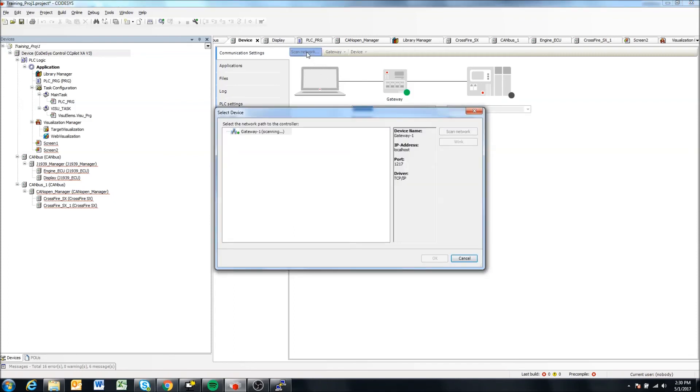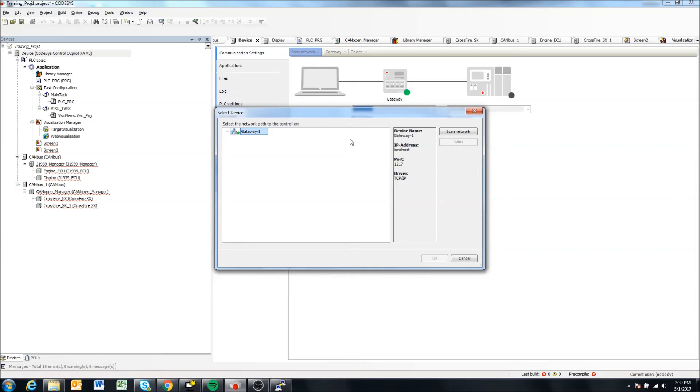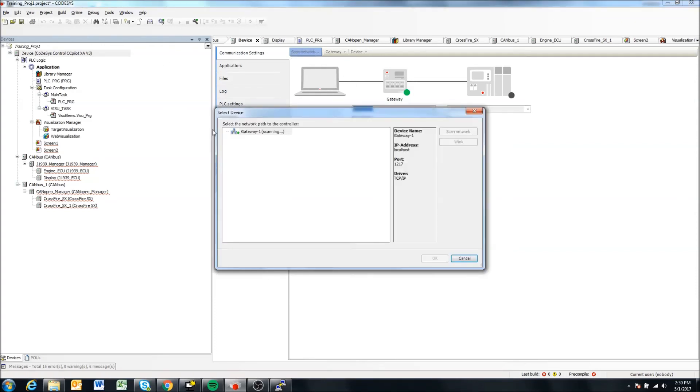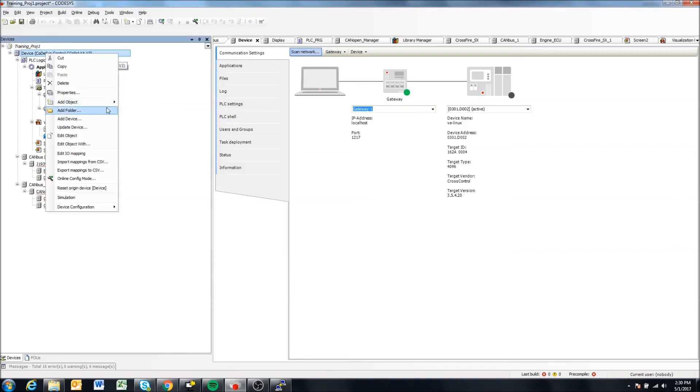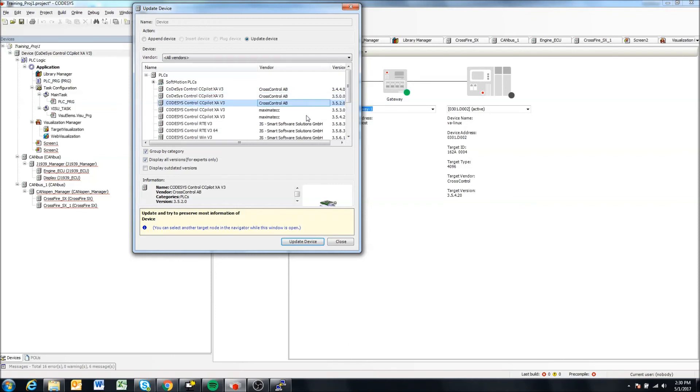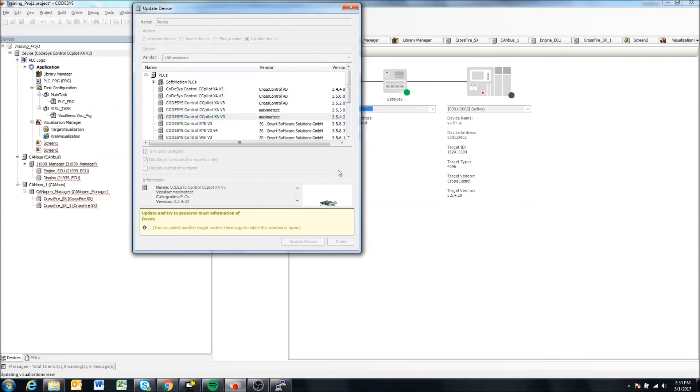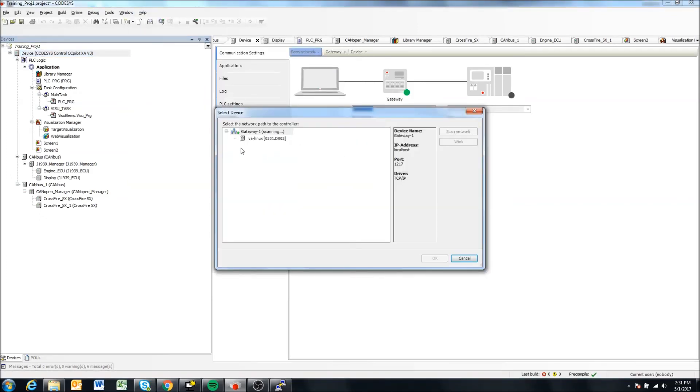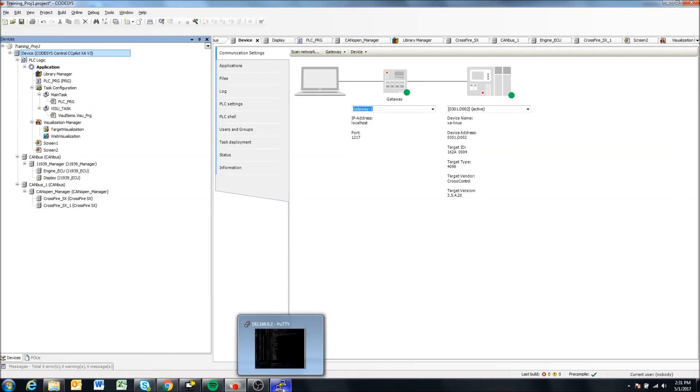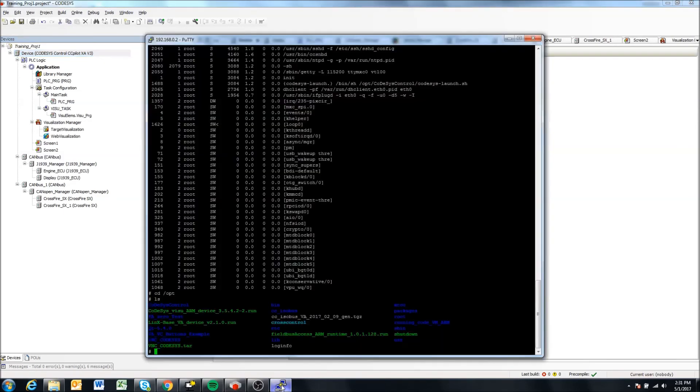And if I now select scan network, you'll notice nothing comes up, because the runtime and the device description file I'm trying to connect to are incompatible. It doesn't see anything that is compatible with it on the gateway. So this is how it could look if you guys have a version mismatch. If I move this, go back here, move it back to 3542. Then our problem should be solved. So now we're back and I see the Linux version. So that's one of the reasons that you could not see your devices showing up.